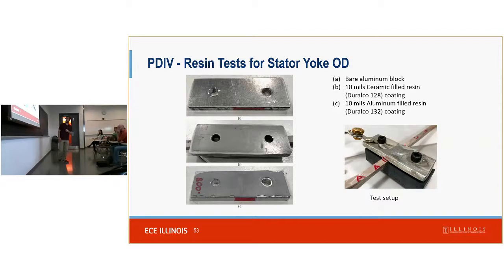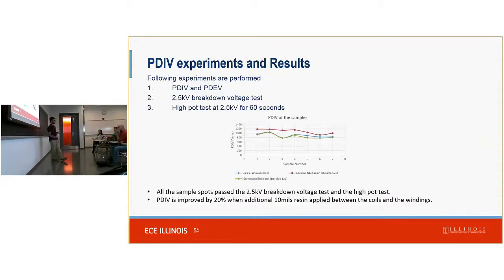Then this is showing additional setup for testing by adding the ceramic-filled resin and comparing that to aluminum-filled resin for that additional 0.010 of an inch of insulation. And here we can see the green line is the lowest. That's the aluminum-filled resin. The blue line is the bare aluminum block. Adding aluminum-filled resin was very similar to, but slightly worse than, just connecting straight to the block. But adding the ceramic-filled resin, which is a much better electrical insulator, actually improved the PDIV, increased the PDIV.